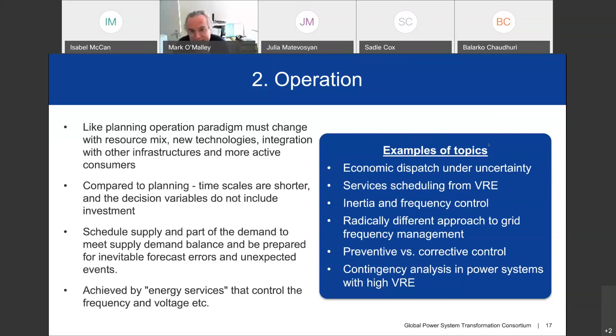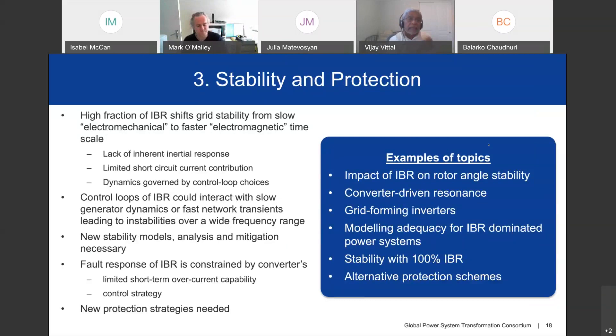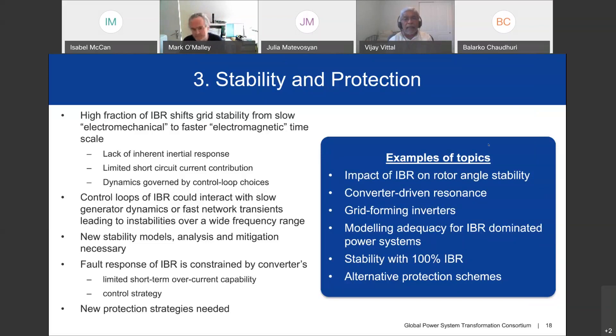Good day, good morning, good afternoon, good evening wherever you are. One of the first topics we are examining in greater detail is stability and protection. The question is: how does a high fraction of inverter-based resources impact stability? There are key issues to look at: lack of inherent inertial response, limited short-circuit current contributions, and dynamics governed by the control loop of choices. We are looking at a number of topics in this area, including alternate protection strategies and how to examine the fault response of inverter-based resources.